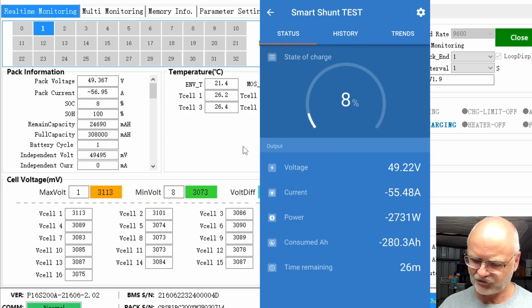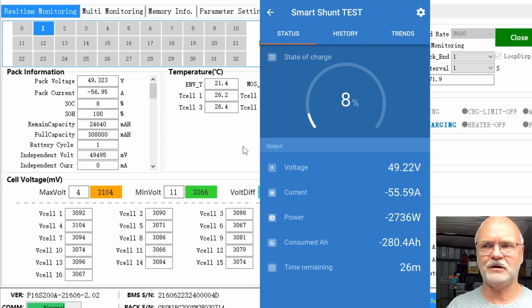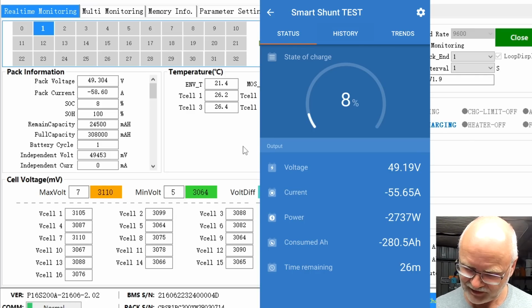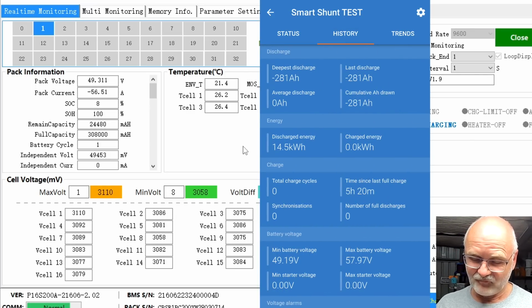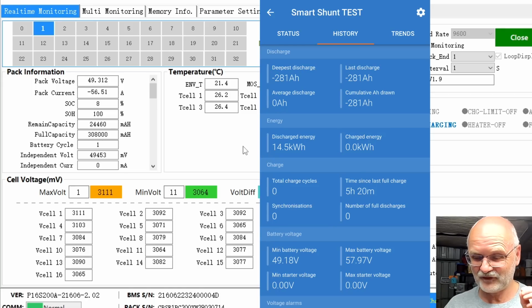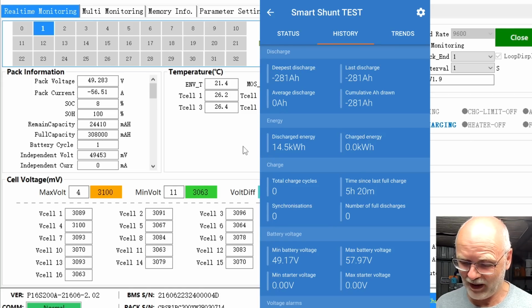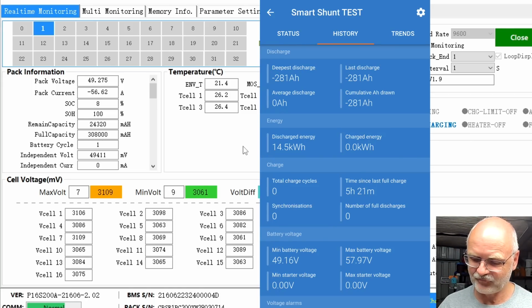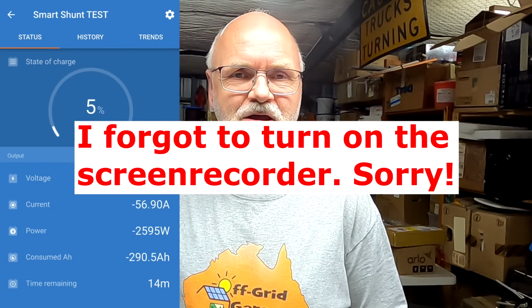Interesting, we have just consumed 280 ampere hours, which is the designed capacity for these LF280K cells. Let's check the history - we've pulled 14.5 kilowatt hours from this battery already. Wow, we're discharging for 5 hours and 21 minutes. Insane test. And we've just reached 290.5 ampere hours of discharged capacity.